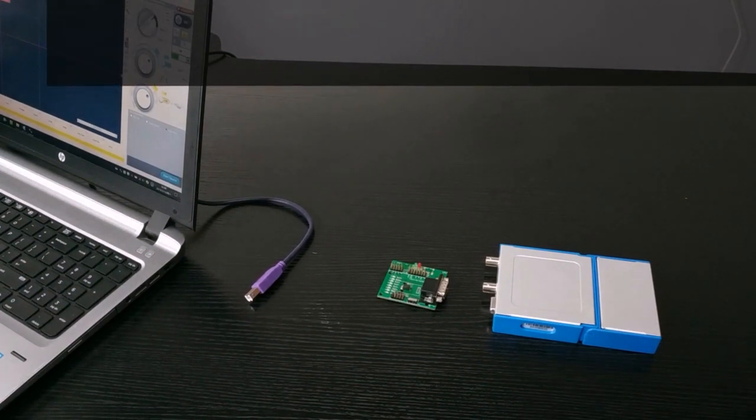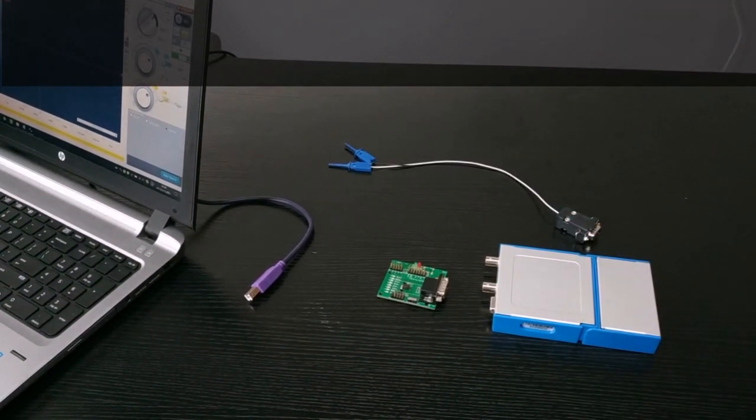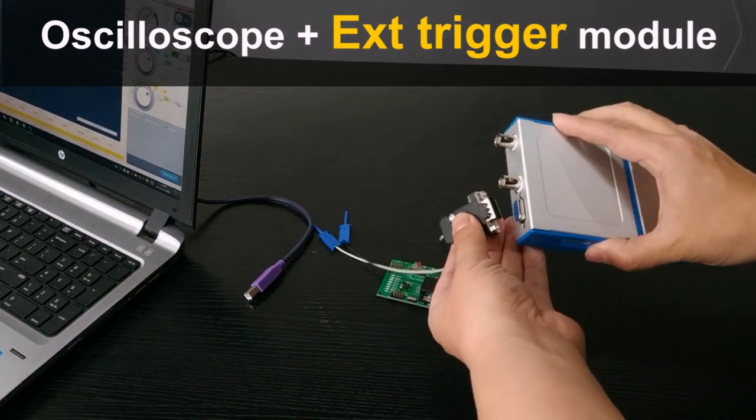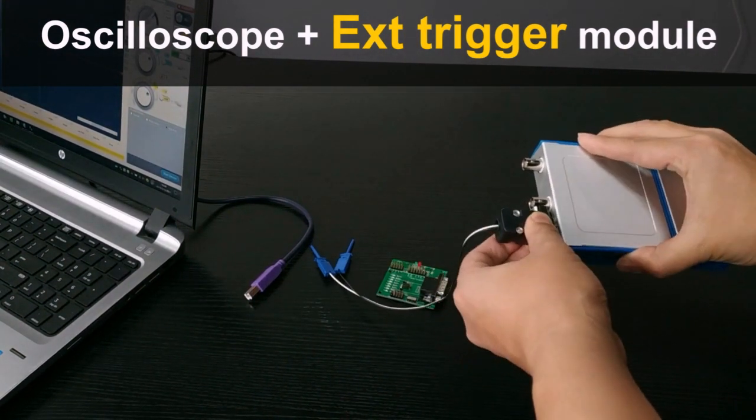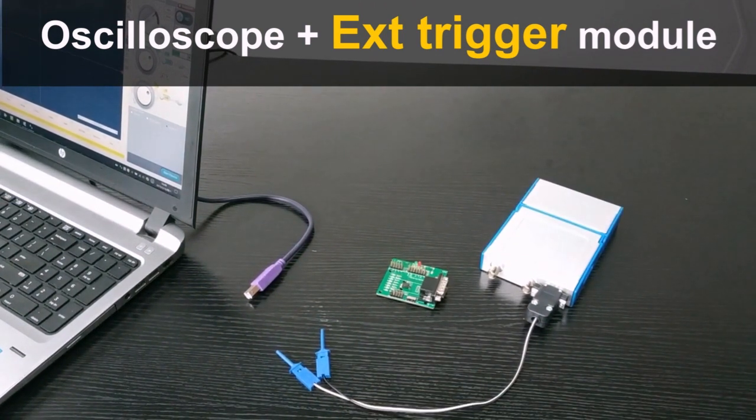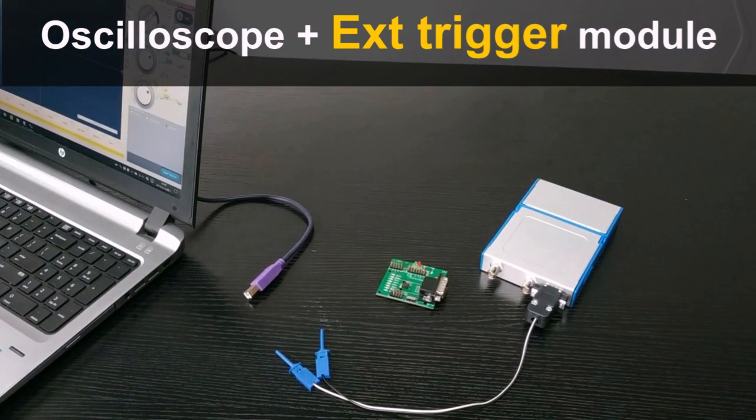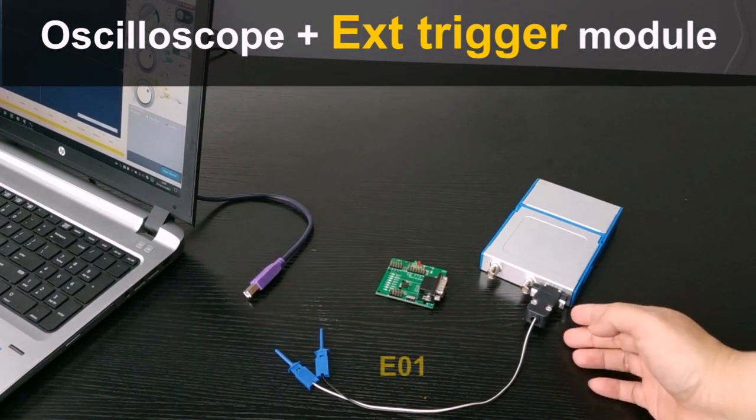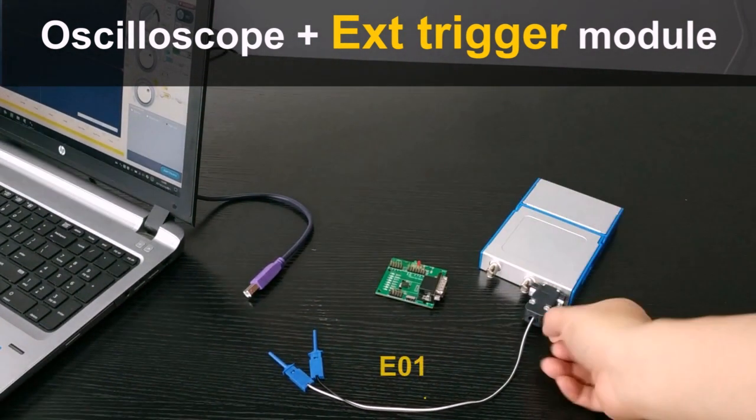For example, this is an external trigger module. So with these modules it is possible to command the data acquisition with an external signal. With this module this oscilloscope now can be triggered from channel A or it can be triggered with an external signal.